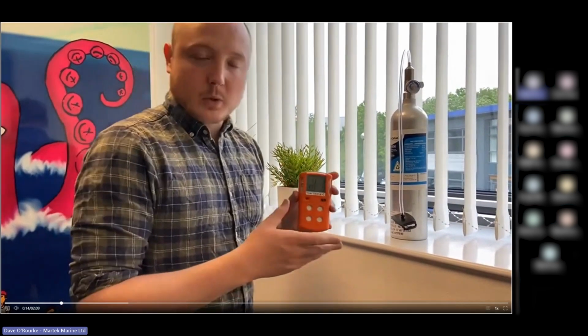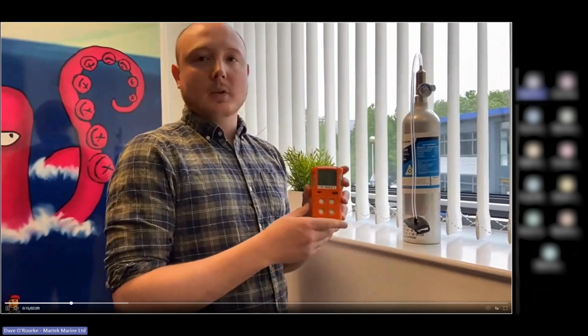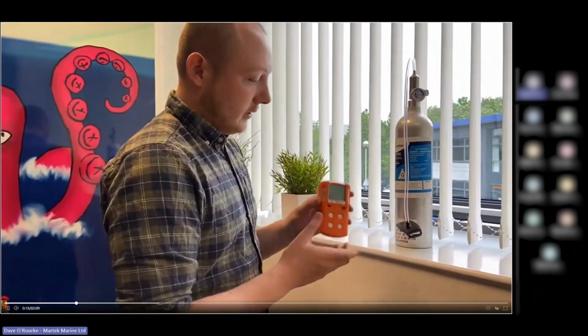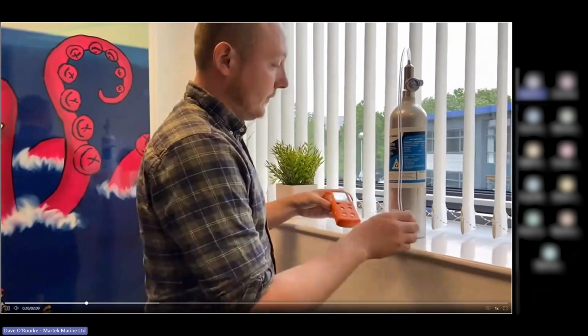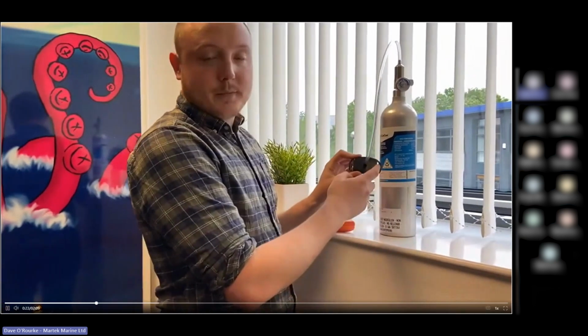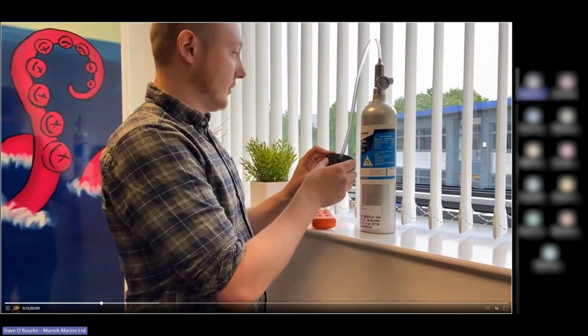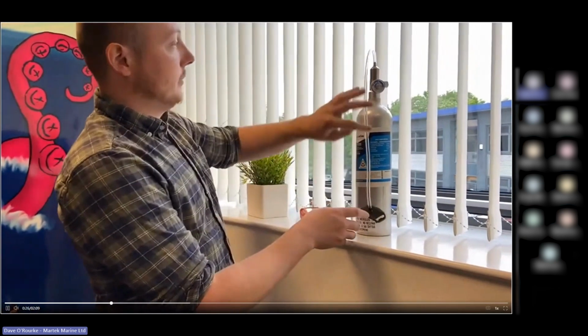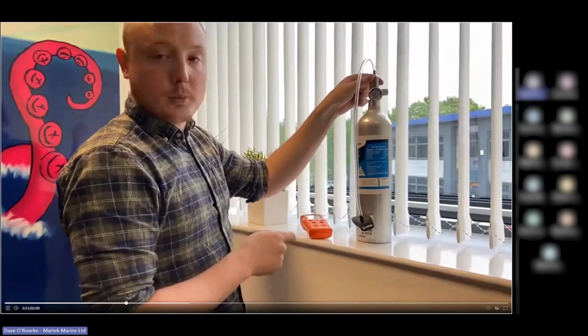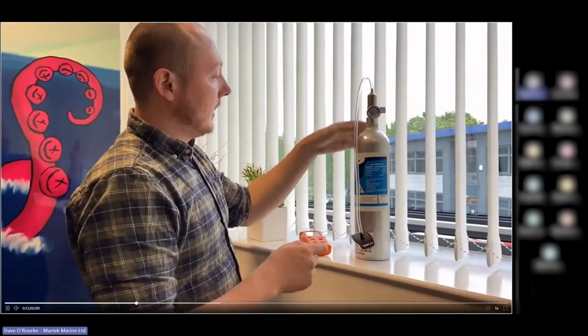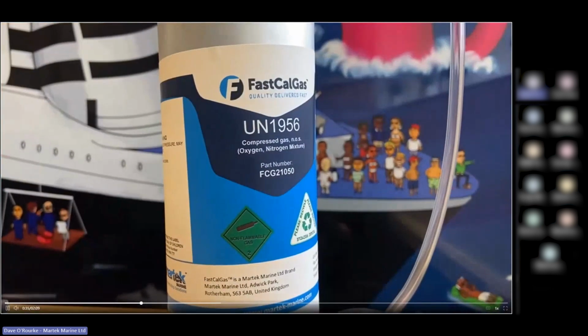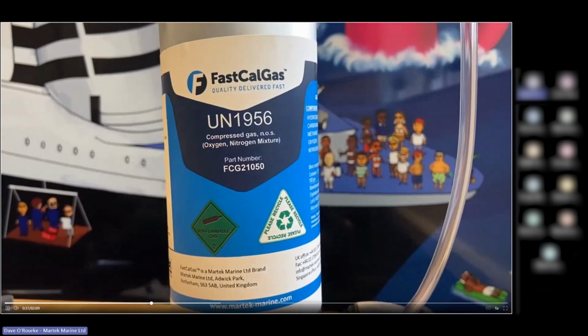In order to bump test, which we recommend doing before every usage, you're going to need a few things: your CCC, the calibration cap which comes with all the CCCs we provide, a little bit of tubing, a fixed flow regulator at 0.5 litres per minute, and a bottle of Fast-Cal gas FCG 21050.